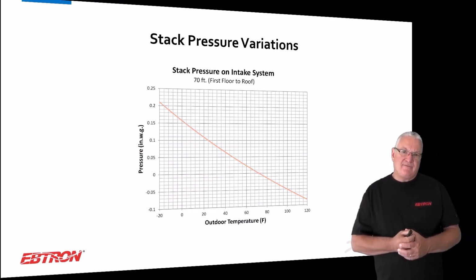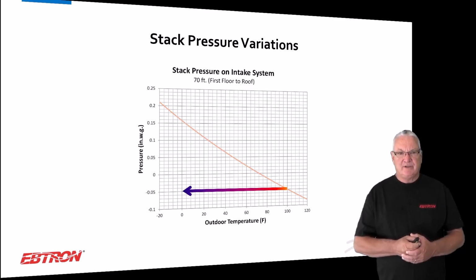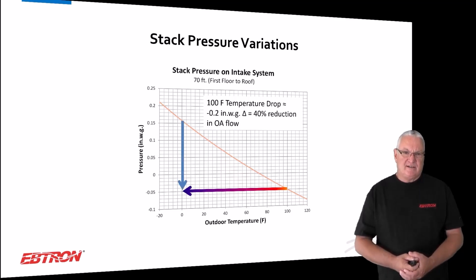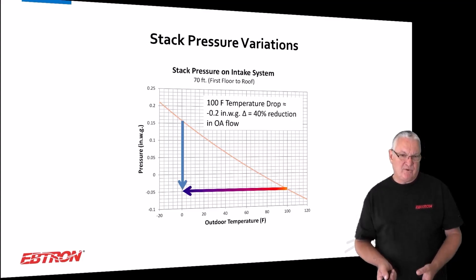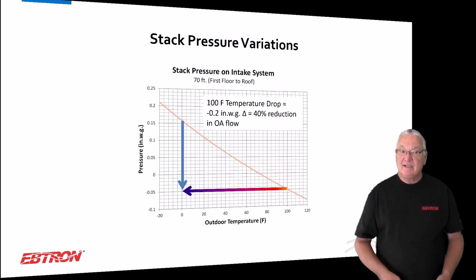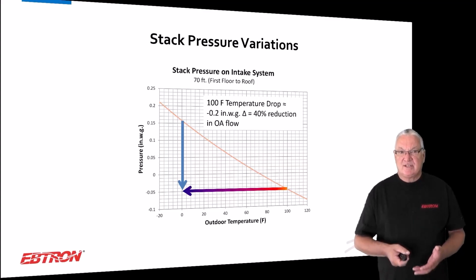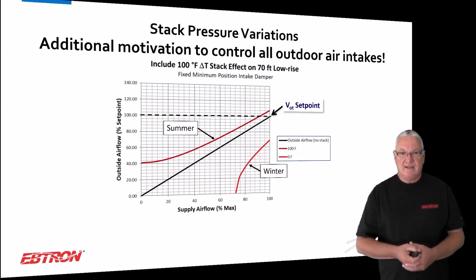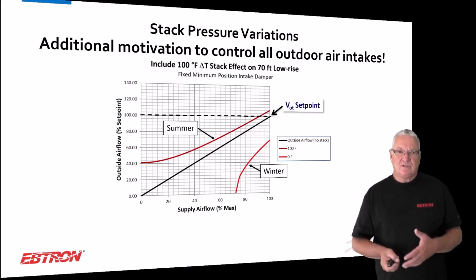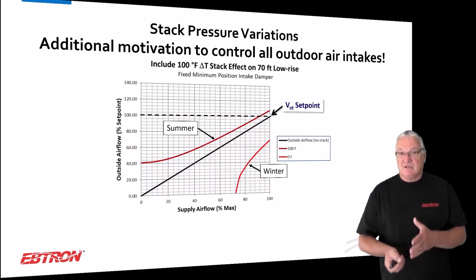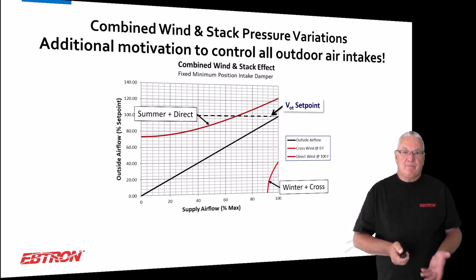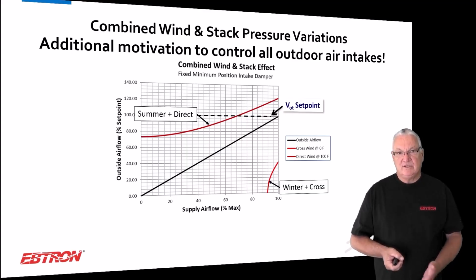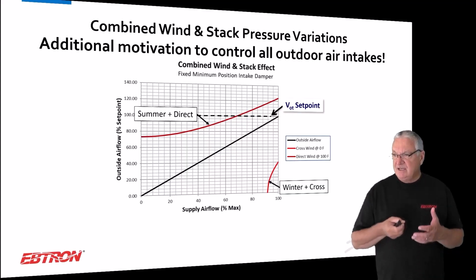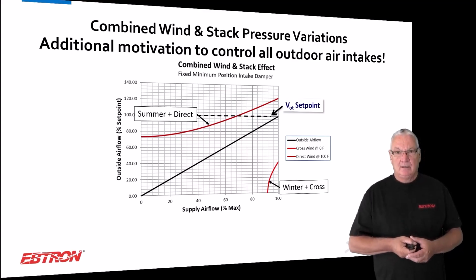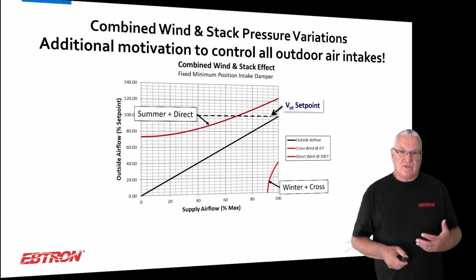Stack pressure, very similar. I have a 70-foot low rise, 100-degree swing in temperature, same 0.2 of an inch. Now, some of you are in cooler climates where you'll see more. Some of you are in more temperate climates where you see less, but the bottom line is it's a problem. And if you just set it and forget it, there's no way to compensate for it, and you get a very similar type of deal. Winter stack problems are worse than summer stack problems, because the offset in temperature is typically more. And when you combine the two, which is really what happens, the wind blows and the temperature changes, really any system that's depending on damper position cannot effectively maintain outdoor airflow rates. It doesn't matter what it is. Okay, so that's what we have to do here.